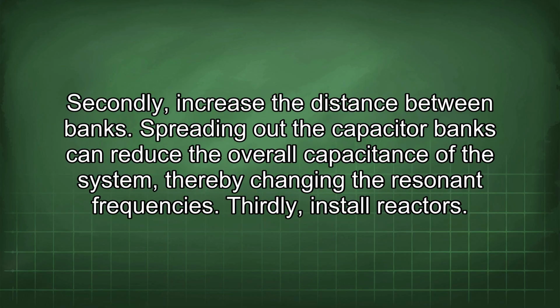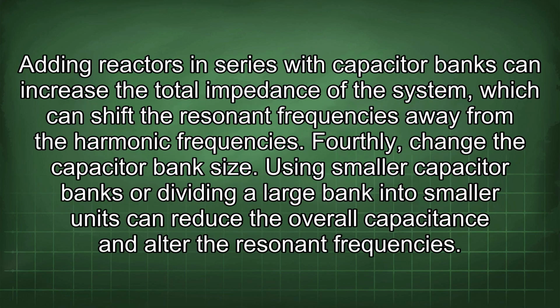Secondly, increase the distance between banks. Spreading out the capacitor banks can reduce the overall capacitance of the system, thereby changing the resonant frequency. Thirdly, install reactors. Adding reactors in series with capacitor banks can increase the total impedance of the system, which can shift the resonant frequencies away from the harmonic frequencies.